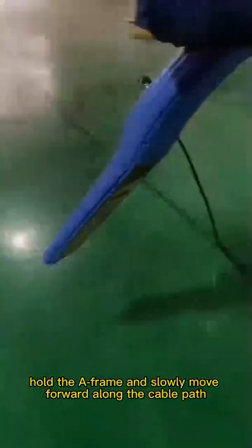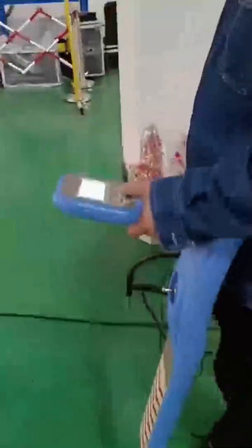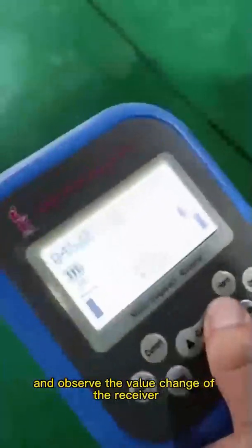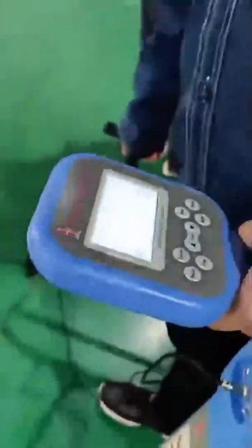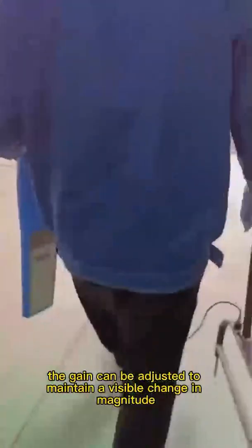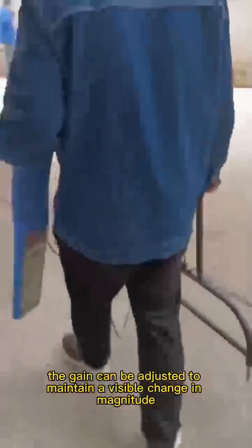Properly adjust the gain. Hold the A-frame and slowly move forward along the cable path. Plug it into the ground every other section, and observe the value change of the receiver. When it is close to the fault point, the signal energy is relatively large. The energy bar is full, and the change value cannot be seen. It is necessary to decrease the gain value until the change value can be seen. During probing, when the receiver starts to sound, the gain can be adjusted to maintain a visible change in magnitude.